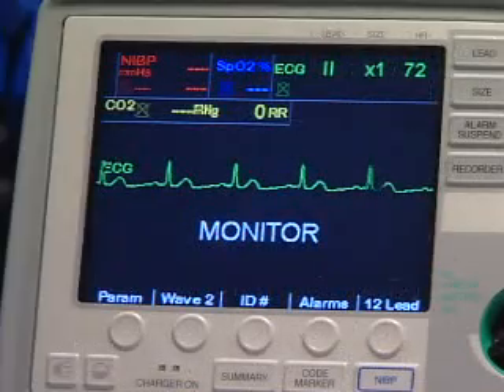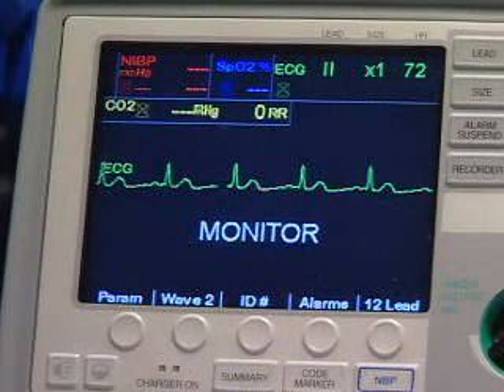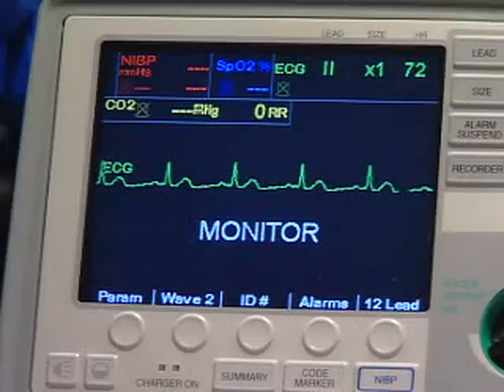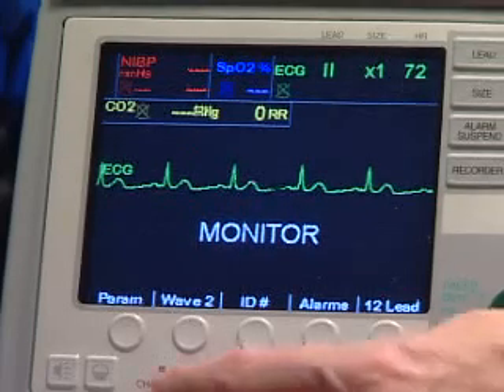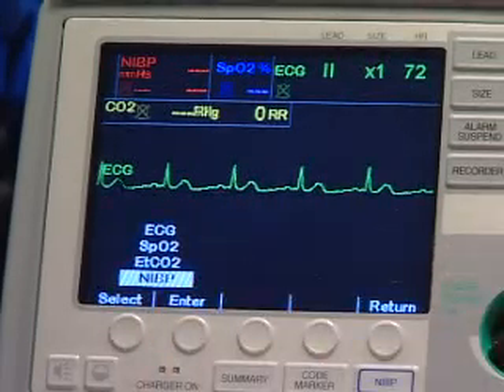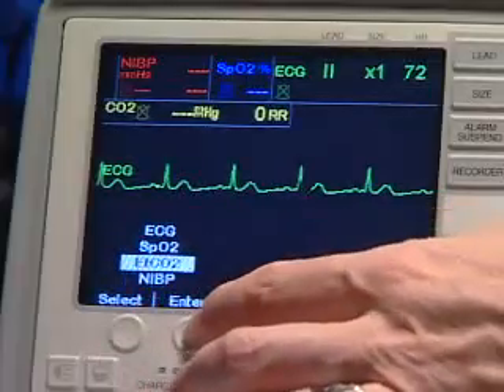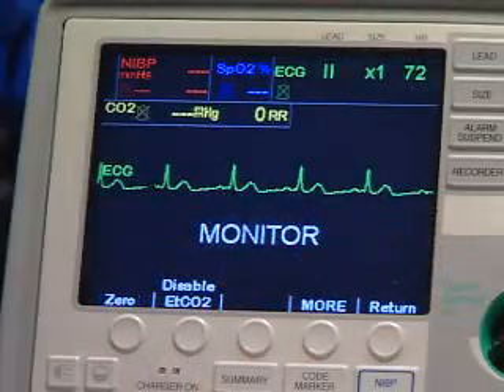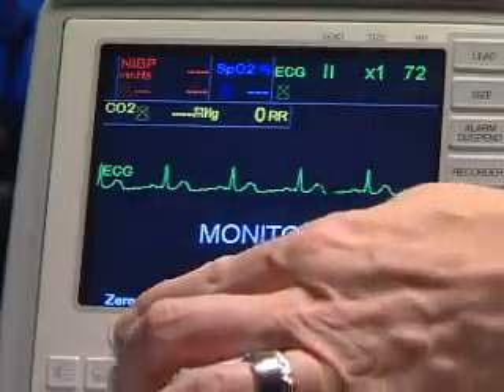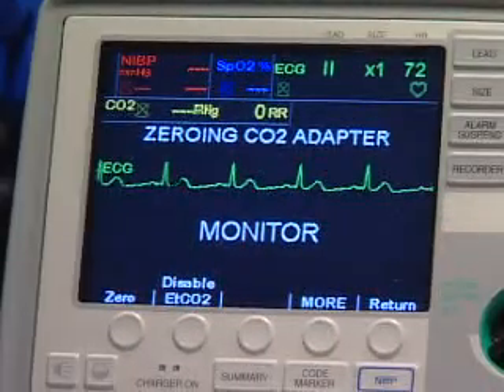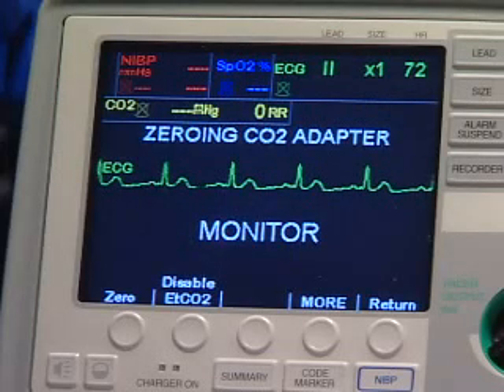Zeroing should be done the first time a particular Capnostat 5 sensor or module is attached to the E-Series, or when changing between reusable and disposable adapters. In order to zero the sensor, press the parameter soft key. Select the ETCO2 menu item, then press Enter. Press the Zero soft key. The E-Series zeroes the adapter and displays the Zeroing CO2 adapter message for 15 to 20 seconds. The unit displays the Zero Done message on the display when complete.